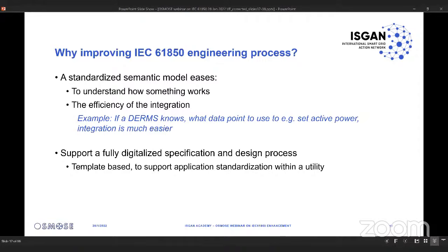For example, if a DER management system knows which data point to use to set active power in each device it has to control, it's much easier than if it needs to find out in every different device which data point is used for the active power control set point. So having a standardized semantic data model not only helps understanding, it significantly helps the integration work.